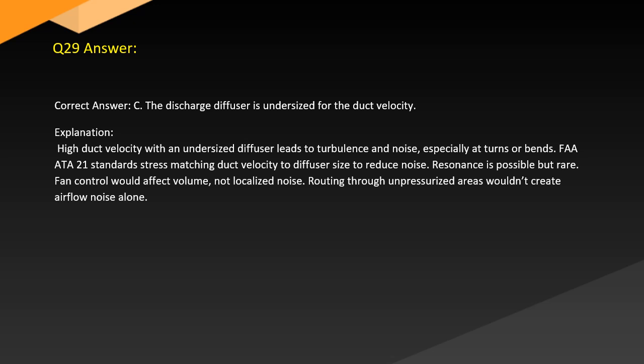Answer. Correct answer: C. The discharge diffuser is undersized for the duct velocity. Explanation: High duct velocity with an undersized diffuser leads to turbulence and noise, especially at turns or bends. FAA ATA 21 standards stress matching duct velocity to diffuser size to reduce noise. Resonance is possible but rare. Fan control would affect volume, not localized noise. Routing through unpressurized areas wouldn't create airflow noise alone.